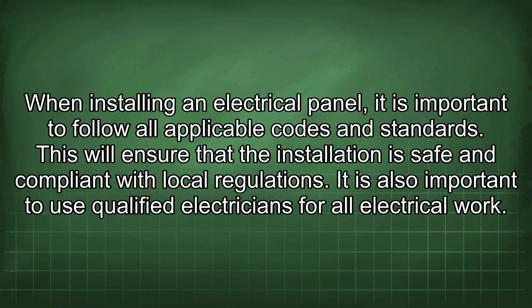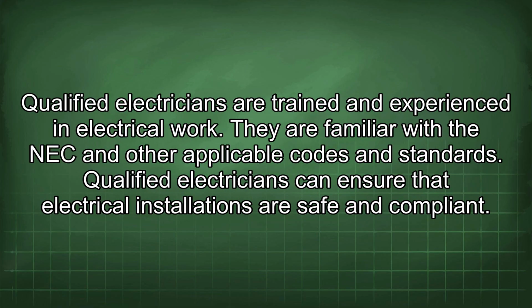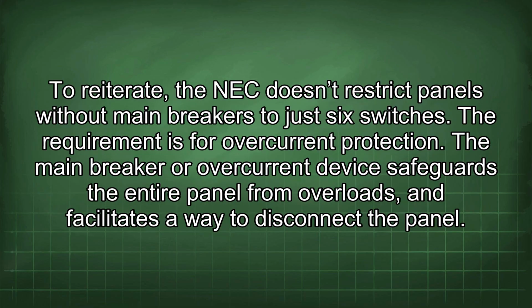It is also important to use qualified electricians for all electrical work. Qualified electricians are trained and experienced in electrical work. They are familiar with the NEC and other applicable codes and standards. Qualified electricians can ensure that electrical installations are safe and compliant. To reiterate, the NEC doesn't restrict panels without main breakers to just 6 switches. The requirement is for overcurrent protection. The main breaker or overcurrent device safeguards the entire panel from overloads and facilitates a way to disconnect the panel.